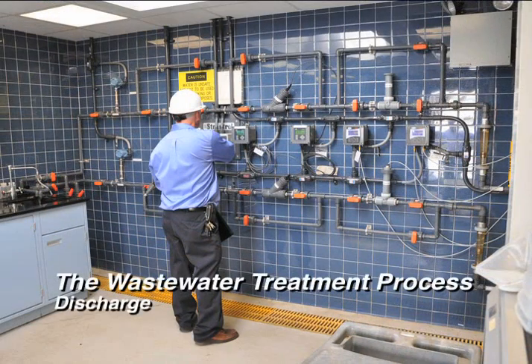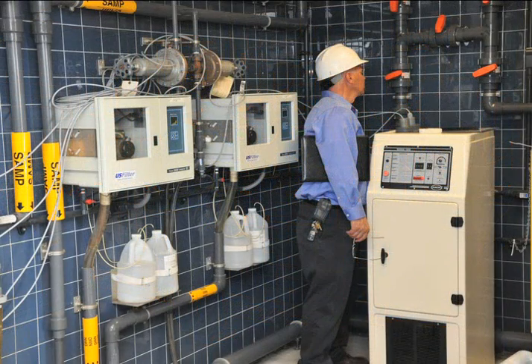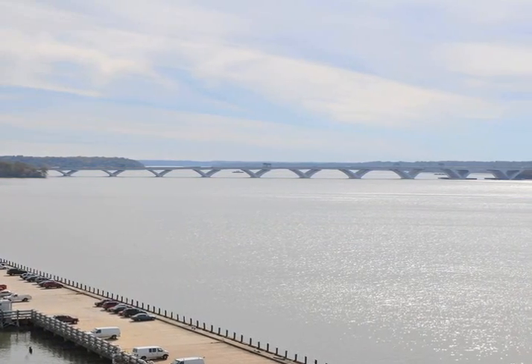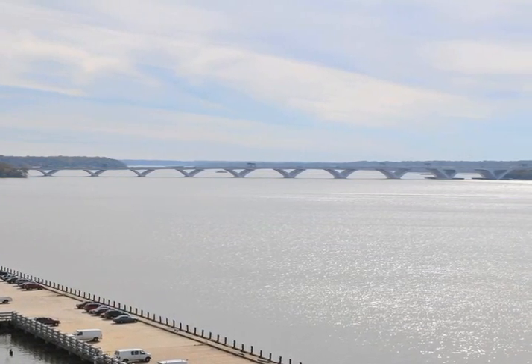After filtration, the flow is disinfected with chlorine to kill the pathogens. Sodium bisulfite is added to the water to remove all traces of chlorine prior to being discharged to the river. After disinfection, the treated wastewater flows out to the Potomac River at the rate of 4,000 gallons per second. The water discharged from the plant is cleaner than the river itself.